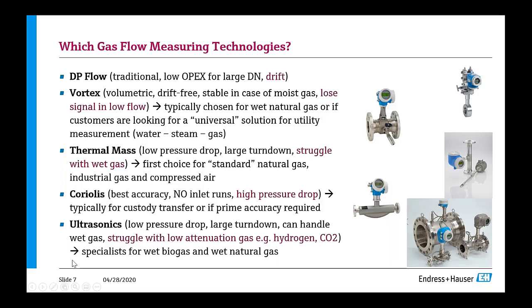So which gas flow measuring technologies are there? First, DP flow is very traditional. You find that a lot in these power plants. The benefit is you have a relatively low operation expenditure, so purchase cost is relatively low for large diameters. However, these guys tend to drift, and you have a limited turn down as well. Then you have Vortex meters. They're volumetric, but usually they're limited in line size up to DN300, 12-inch, and they lose the signal at the low flow. So it is an important technology for steam, but also for water and gas.